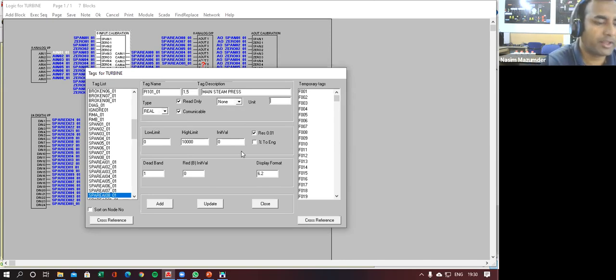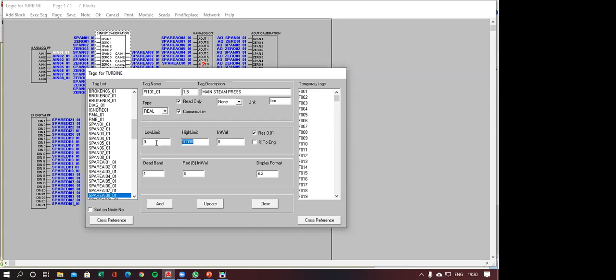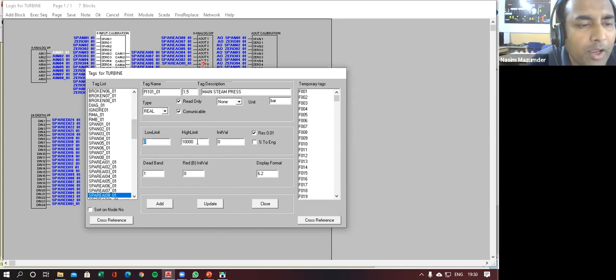Now what will be the unit? Since it is a pressure transmitter, suppose my unit is bar. I can write it as bar. Now you see here, we can set the low limit and high limit. These are counts: the low limit is 0 and the high limit I am writing as 10,000. That means it will have 10,000 counts. The signal received by the PLC will be divided into 10,000 counts, and then it will be calculated once again and displayed in engineering units. The display format says 6.2, which means there will be some decimal places.